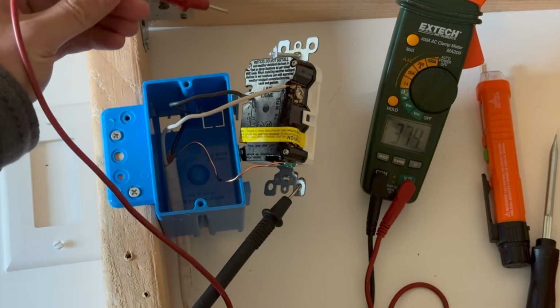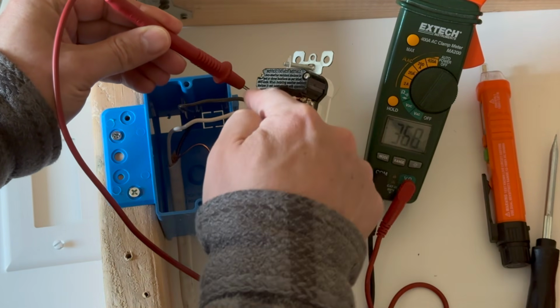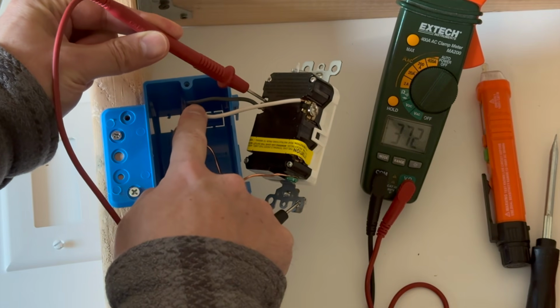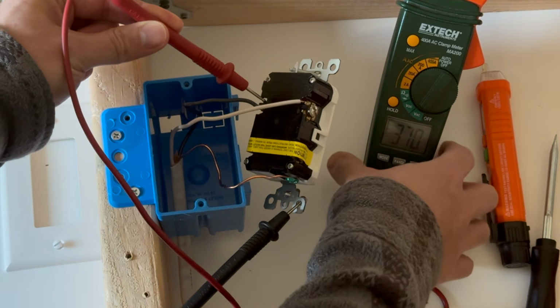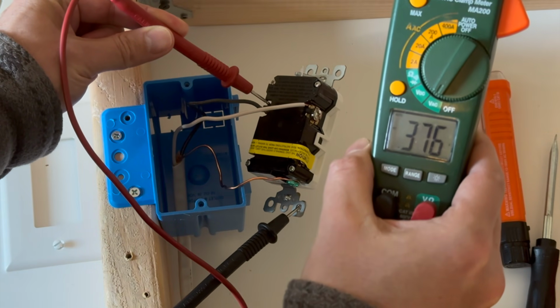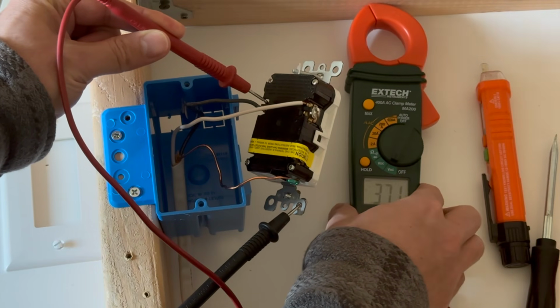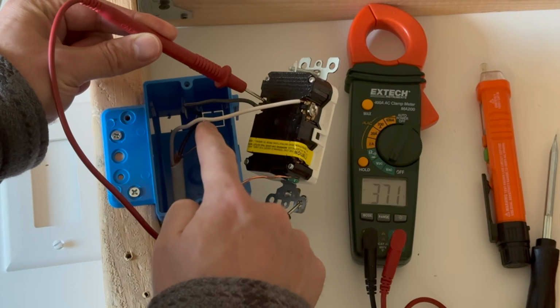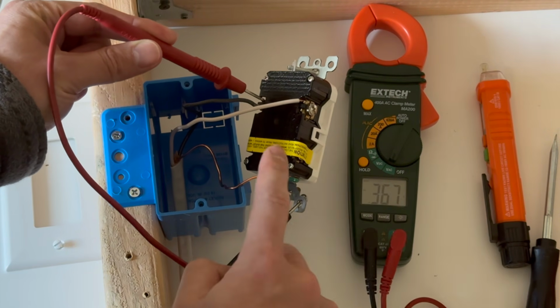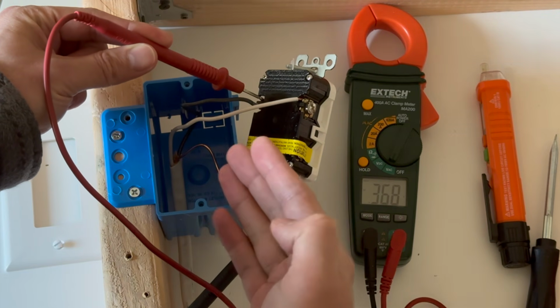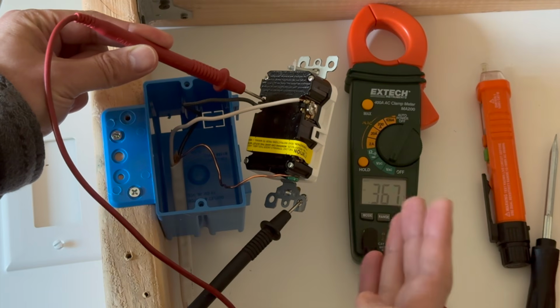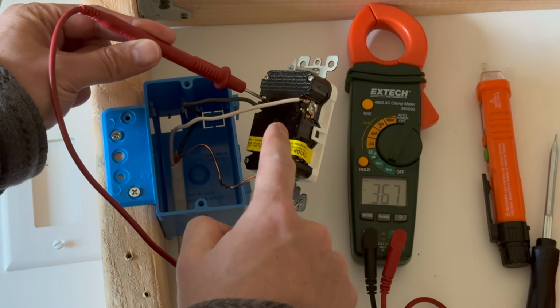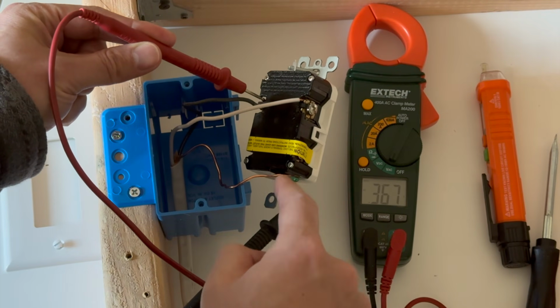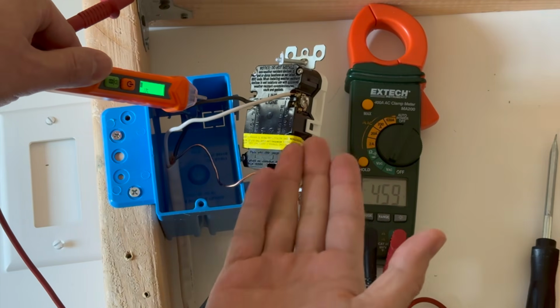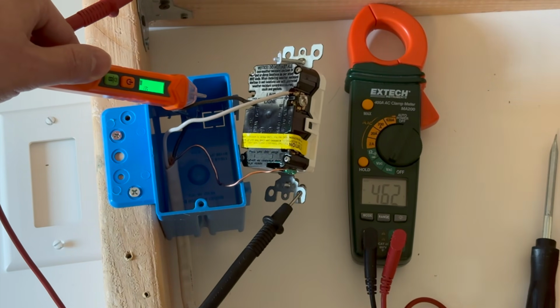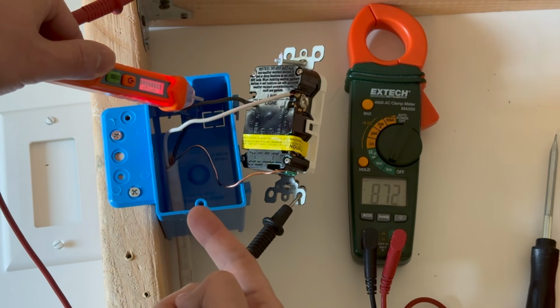And then with one of my hands, I will try to touch the hot terminal. You can see over there, I'm touching the hot terminal, the black wire terminal. And I'm seeing 0.3 on my voltmeter. So in that instance, if I have 0 reading on the wire and I'm not able to reset, it doesn't mean that outlet is bad. It means I have to go further, take a look at the circuit breaker, maybe check the circuit breaker, or there are times this outlet is switched. In my case, this outlet is switched. I know this outlet is switched because, okay, I set it up for a garbage disposal, let's say. I go turn off the switch and it has no power now, okay?